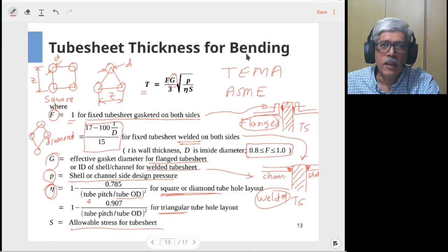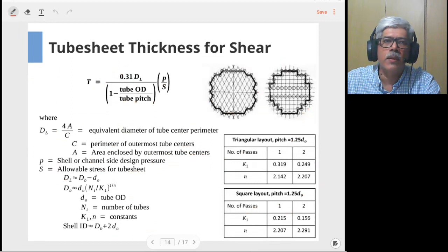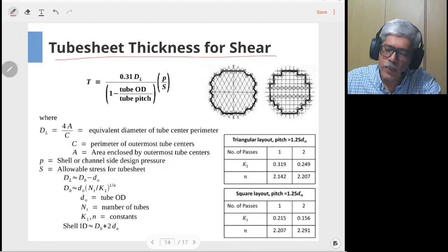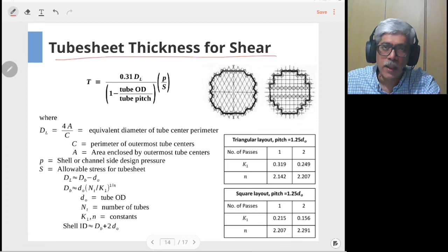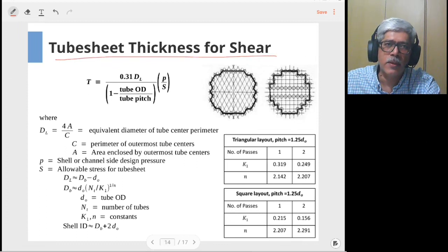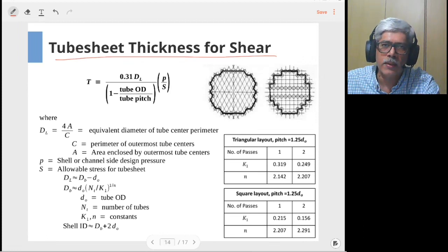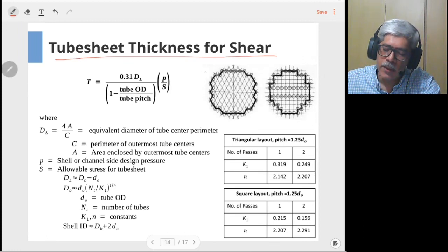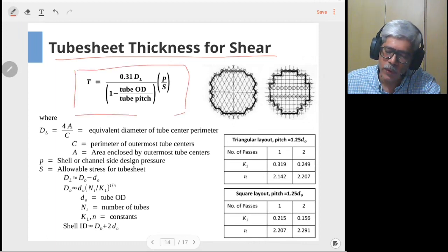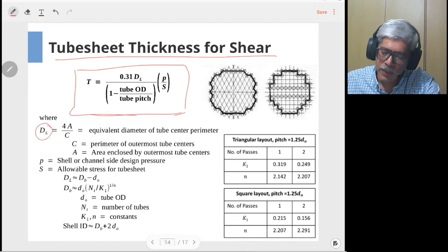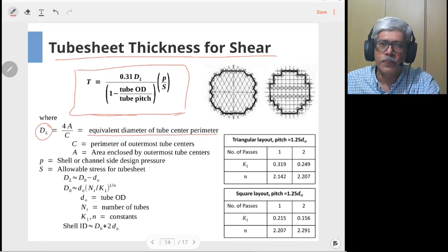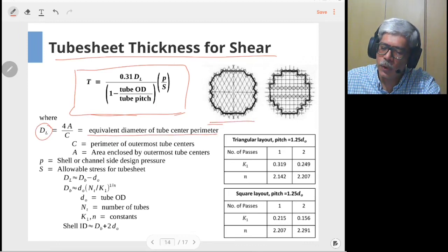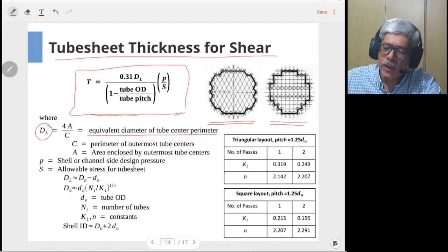Now let's move to the tube sheet thickness based on shear calculations. The tube sheet can fail either in bending or in shear. Here we are considering only the mechanical loads — thermal expansion loads are not considered as that leads to more complex calculations. In the shear formula, there is a parameter DL, the equivalent diameter of the tube center perimeter. The tube hole layouts are shown on the right-hand side: triangular on the left and square on the right.